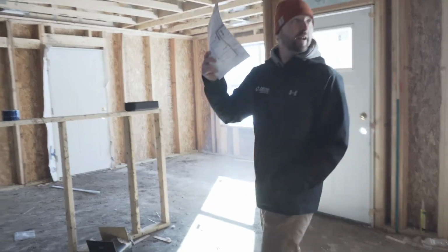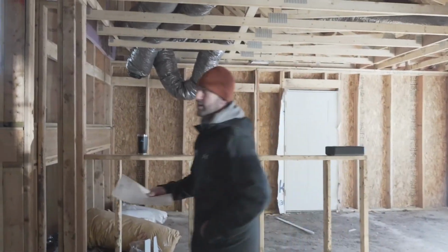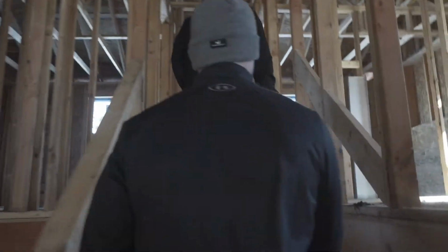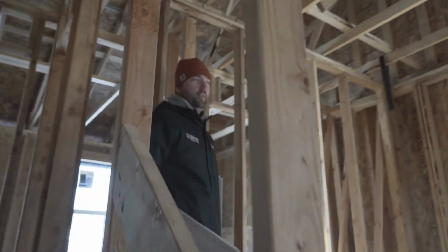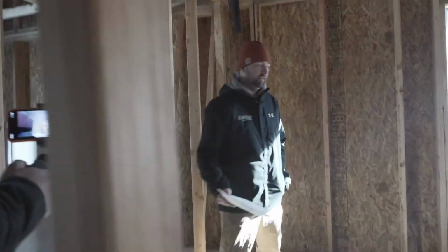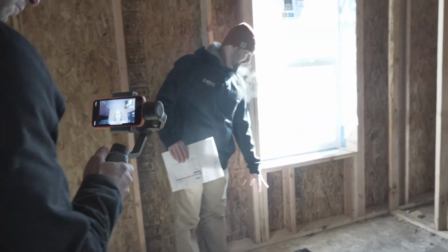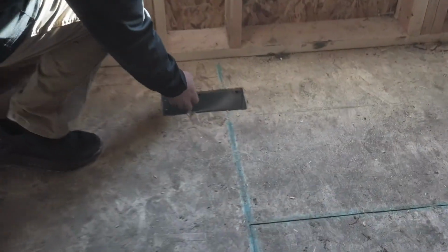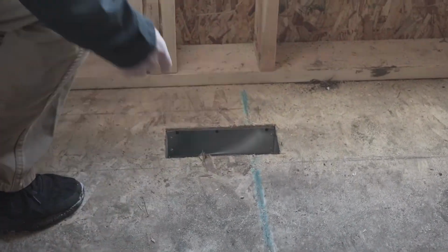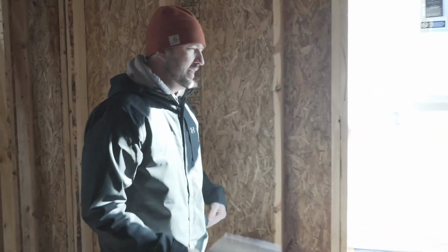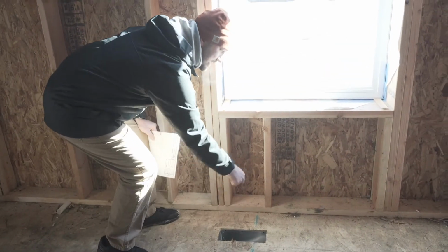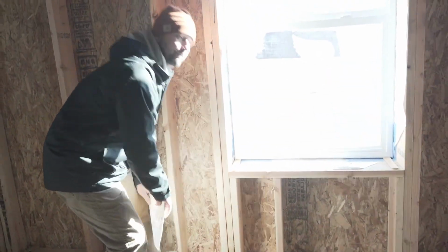On top of hanging your flex work and hanging your boots, now we're into the floor-to-floor side of things. We put a template down, mark this all out, and then cut a 4x10 hole, and then hang a sheet metal boot and nail it to the subflooring. Now that there's a hole there, when they lay carpet or anything down, they'll be able to feel that, cut it out, and that's where they put the register.